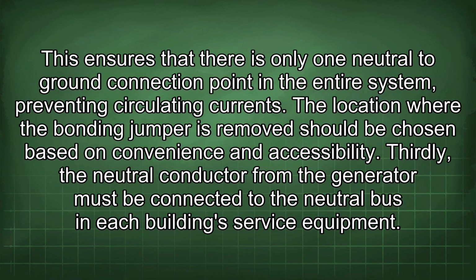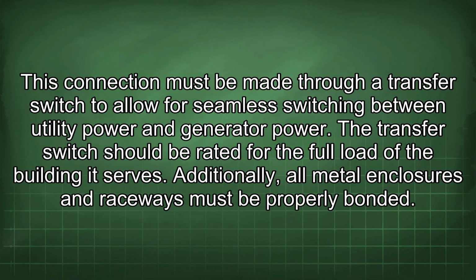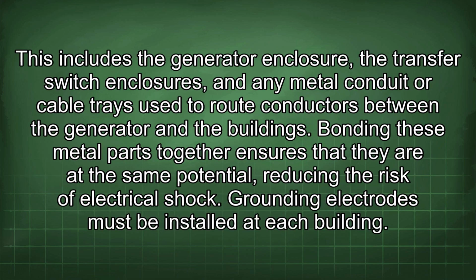The location where the bonding jumper is removed should be chosen based on convenience and accessibility. Thirdly, the neutral conductor from the generator must be connected to the neutral bus in each building's service equipment. This connection must be made through a transfer switch to allow for seamless switching between utility power and generator power. The transfer switch should be rated for the full load of the building it serves. Additionally, all metal enclosures and raceways must be properly bonded. This includes the generator enclosure, the transfer switch enclosures, and any metal conduit or cable trays used to route conductors between the generator and the buildings.